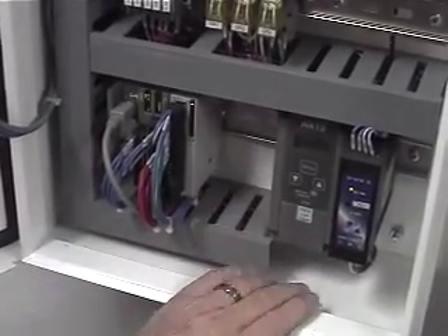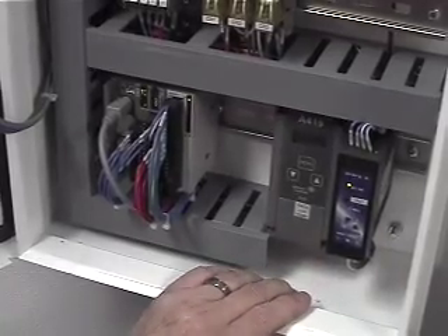This little guy right here is what we call the backup temperature. In programmable logic, we know if we've lost the analog input card, which is this guy right here. So if both your RTDs go down or your analog input card goes down, it's going to go into alarm, and the interface or the status line is going to say, hey, you got big problems.